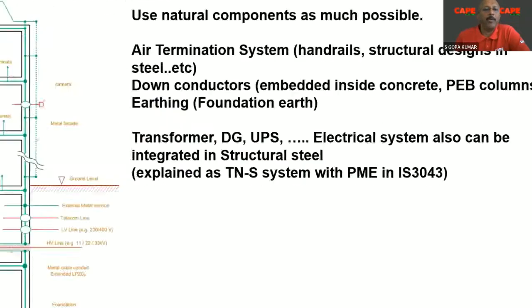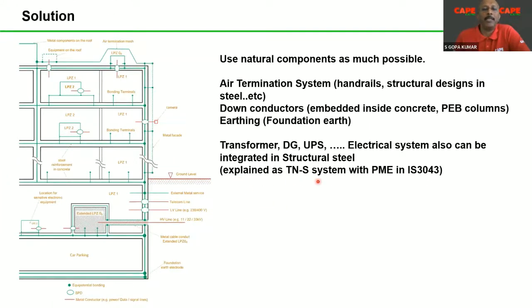Now, when it comes to the earthing of DG, UPS and the electrical system, you can also use the natural component. This is explained as the TN-S system with PME in IS 3043. Across India, we have designed, executed and tested probably more than 100 large multi-storied buildings and large industrial buildings with this technique, where there is no earth electrode in soil. The transformer neutral is connected, transformer body is connected, DG is connected, UPS is connected, lift is connected, your electronic installations are connected, BMS is connected, everything integrated into the natural material. That is the best and recommended method, which is included in the IEC standards.